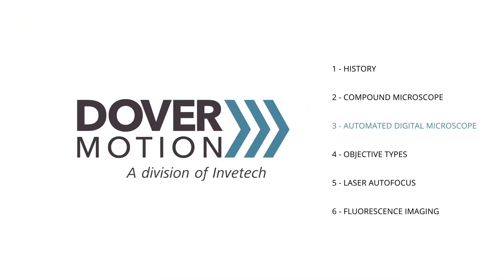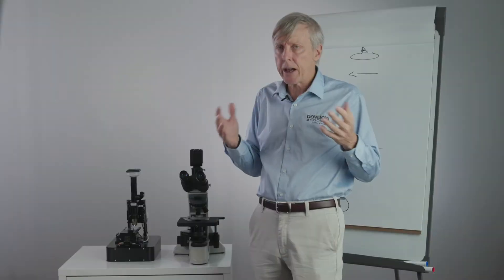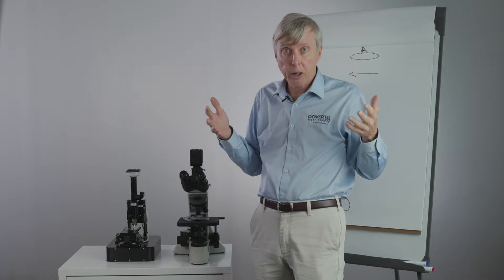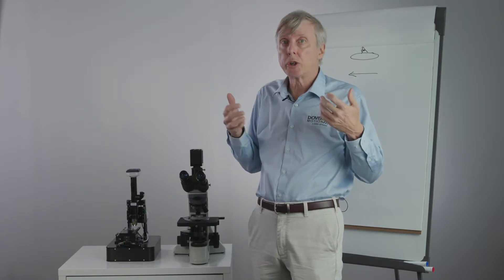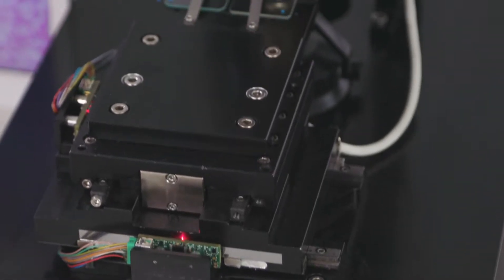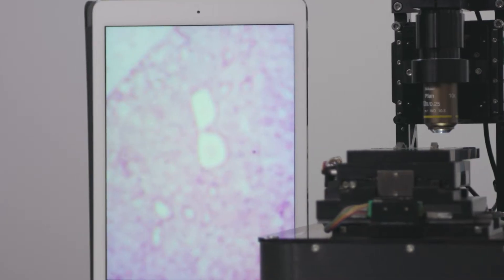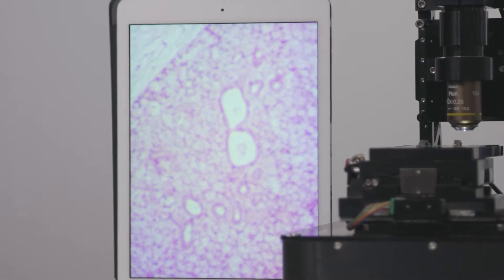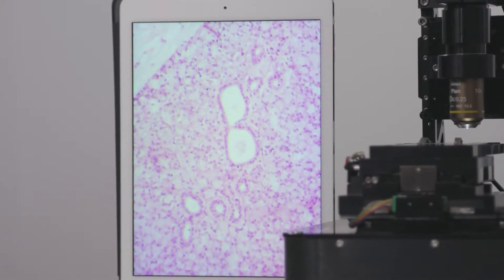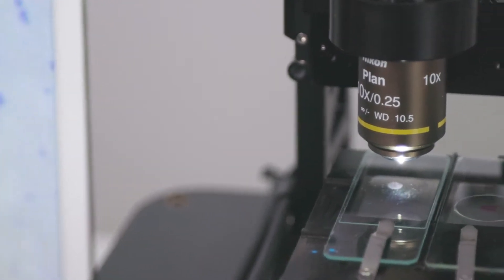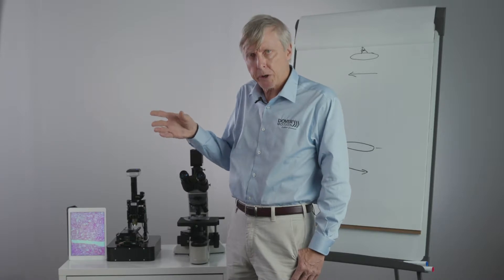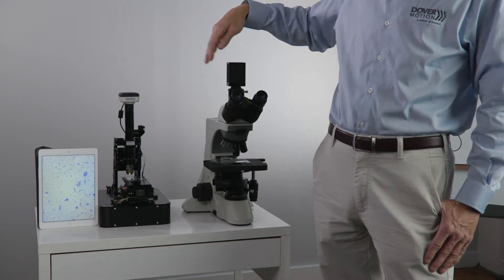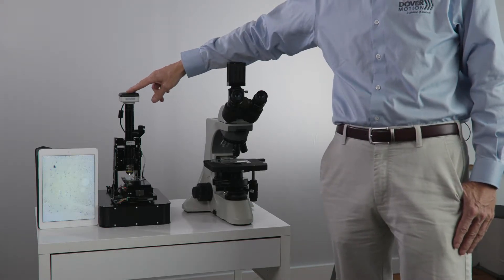These days, automated digital microscopes are at the heart of a vast array of modern biomedical, life science, and diagnostic instruments — from pathology scanners to DNA sequencers to cell imaging. On the left we have an automated digital microscope currently going through focus, finding the best focus, snapping back to it, and moving field to field. It consists of a programmable high-precision XY stage, our DOF5 focus stage (Dover Objective Focuser, 5 mm stroke), providing automated focusing and XY motion, with a CCD camera replacing the human eyeball.